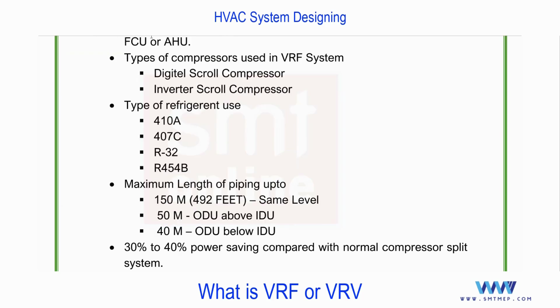You know, in a split system, the maximum length of the pipe between indoor and outdoor, as we discussed, is 25 to 30 feet, or for some manufacturers, as per the capacity, it may be up to 15 meters. 15 meters is nearly 45 feet. That depends on capacity, because if you talk about the split cassette type with 4 TR, since splits are available up to 4 TR, with 4 TR the pipe length may be up to 45 feet, nothing but 15 meters. So the limit for the split is 15 meters, and that too as per the capacity, not for all. For 1.5 to 2.5 TR, you may get 25 to 30 feet, not more than that. But in the case of the VRF system, the limit is up to 150 meters.